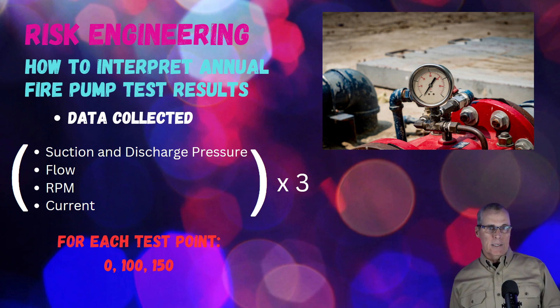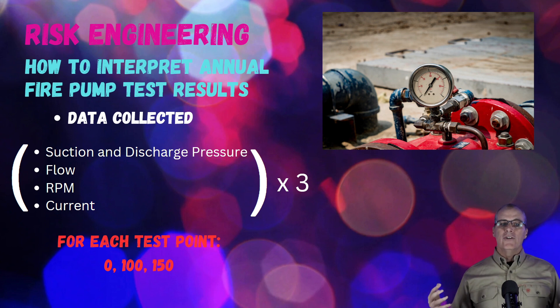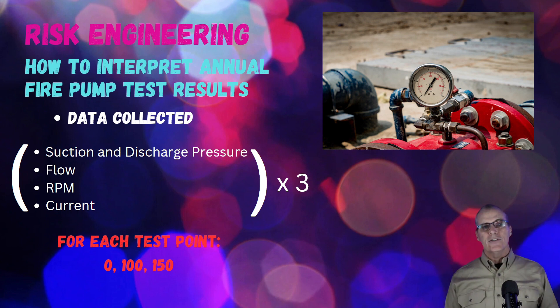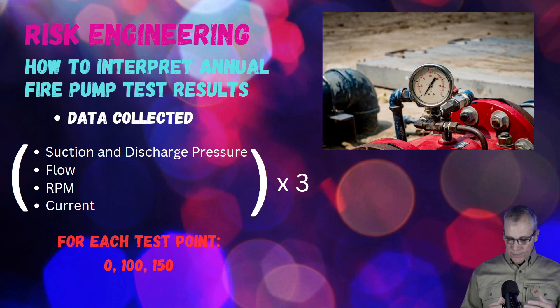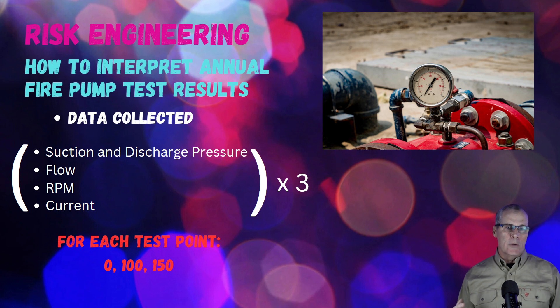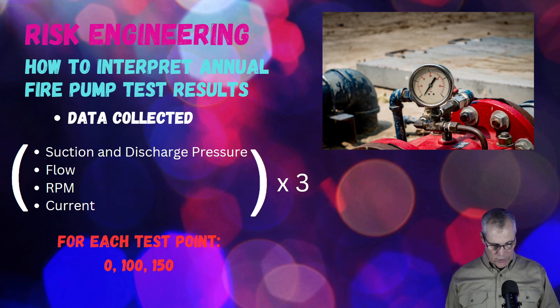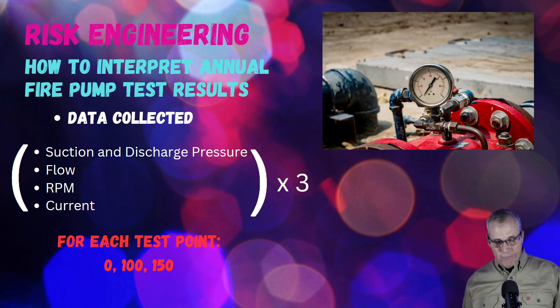What data gets collected during a fire pump test? The suction and discharge pressures, the flow — we'll talk about how we measure the flow — the RPMs, and the current. These are the basics; there's more that gets looked at and I urge you to go back and look at NFPA 25 to do a complete, proper fire pump test. We're here to learn how to interpret the results of those tests.